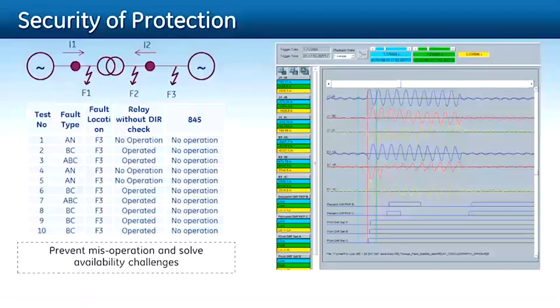Again, in terms of proof points, you should be able to test your transformer protection relay and look at the performance for various conditions of true and false. So in this case, I'm showing an example of, again, the same system of a transformer fed by both end sources in RTDS and creating various types of faults. In this case, F3 is the fault that is outside the zone of the transformer, and you create different varied degrees of CT saturation. You are simulating real-time system behavior in a modeled environment, and you actually subject your relay through this test. And you can see a relay without directional check and CT saturation operates for an external fault about 70% of the fault cases, whereas an 845 is stable for all those fault conditions. That's really powerful in terms of true false stability.